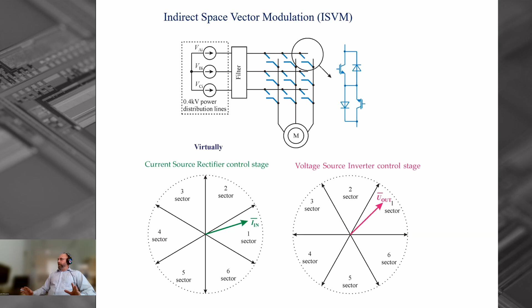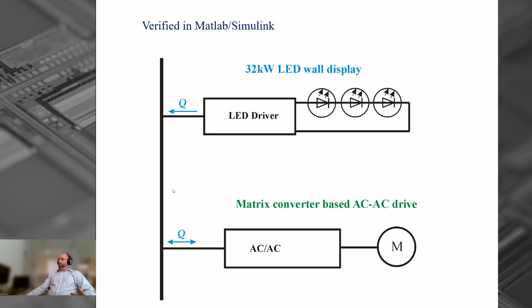of this converter's connection to the power distribution line, allowing the drive to directly control reactive power. It works as a reactive power compensator because the LED lighting devices produce negative reactive power to the power distribution lines. The matrix converter based variable frequency drive can take this reactive power and make the reactive power at this point equal to zero.